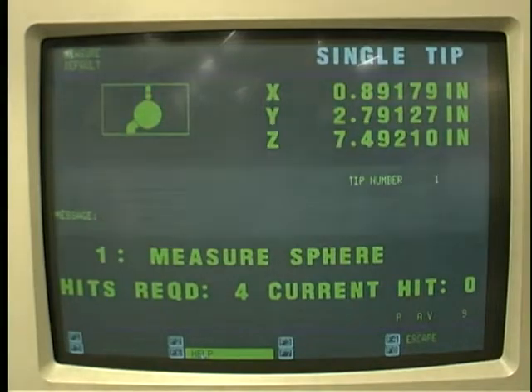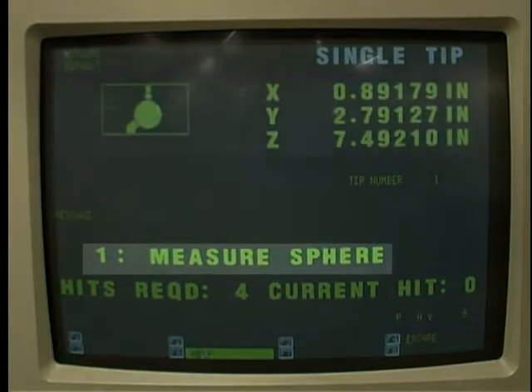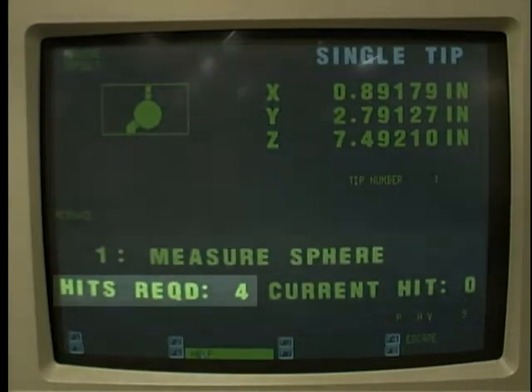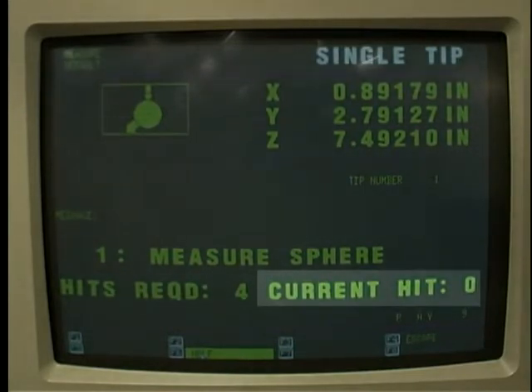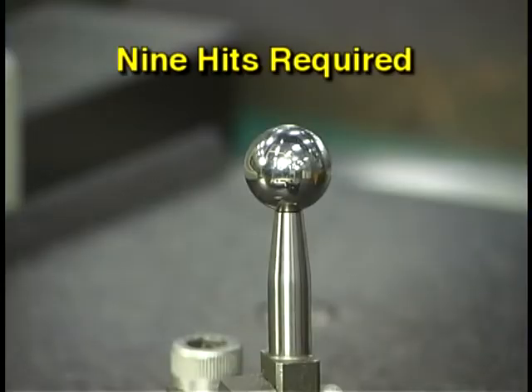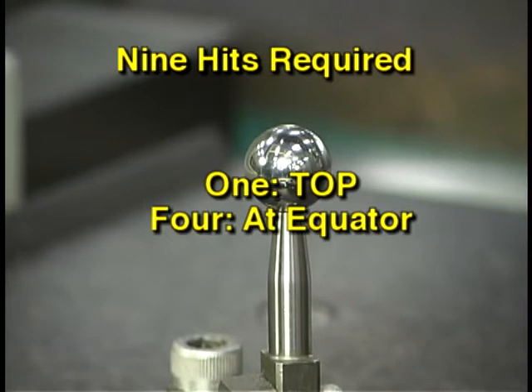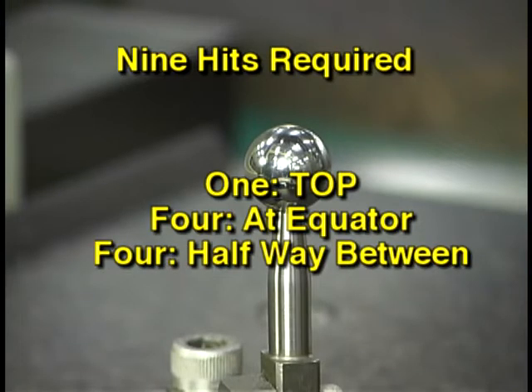The screen displays the procedure for completing the qualification. In step one, the sphere must be measured. To perform this accurately, the software recommends a minimum of four points be measured when checking a sphere. To the right, it indicates that zero current hits have been entered at this time. For this CMM, a minimum of nine points must be read on the qualifying sphere. These points include the top of the sphere, four points around the equator, and four points halfway between the equator and the top.